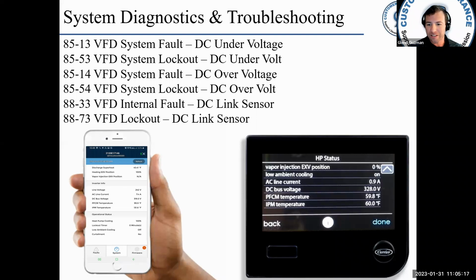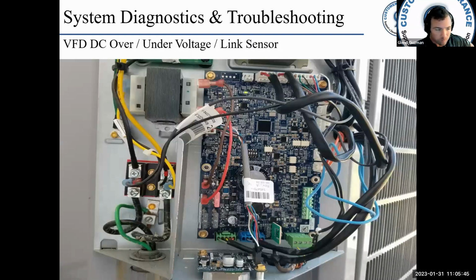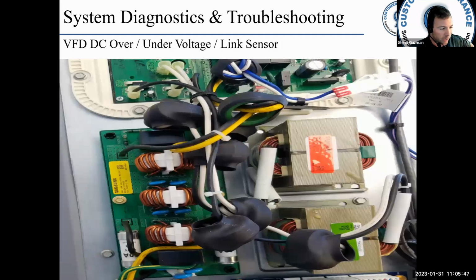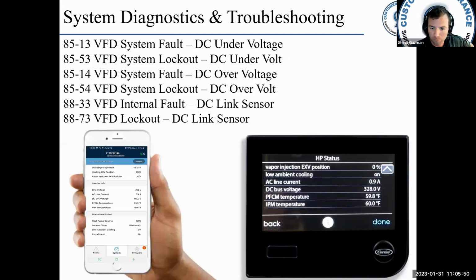8833 is DC link sensor, and 8873 DC link sensor lockout. Again, troubleshooting these codes is all done the same way. You want to make sure you have your high voltage to the equipment. Make sure it's getting up to the drive through the filter board. Make sure your UI and your app are both reporting the correct voltage compared to what you're reading. Okay. Yeah, again, backing up a little bit here.